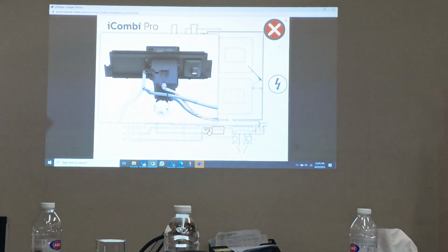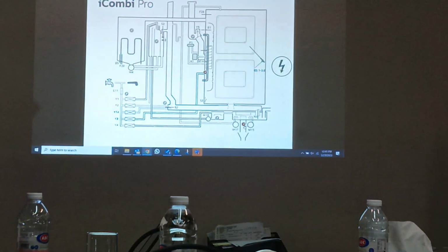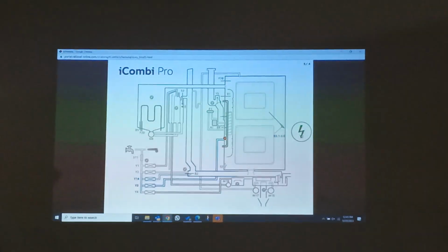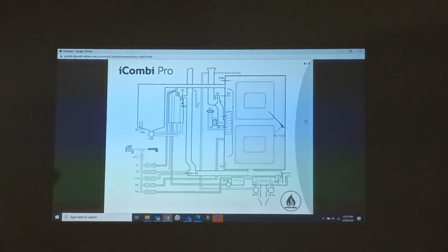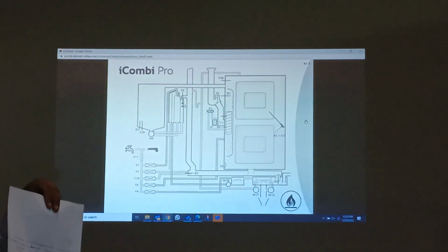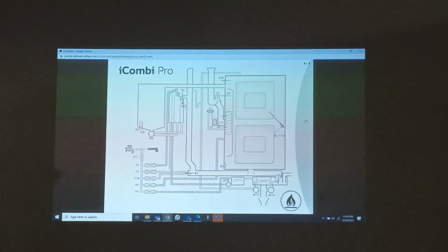The K basket. Drain box, drain pump, circulation pump. Can we make a drain connection higher than the drain line, as we have a drain pump in iCombi Pro? No. We still need a minimum 3 degree slope in the drain line. Right? So the drain pump just takes the water from the drain box and gives it to the drain line. That's it. And from the drain line, the water goes with the help of gravity.